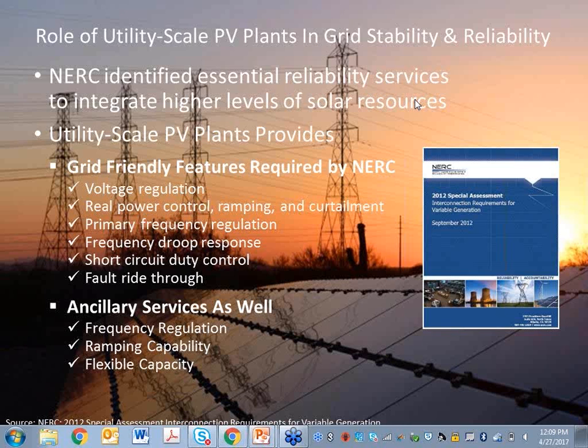What was the maximum power rating for the inverter that has been used? The inverters are 4 MVA. That's why we call it 4 MVA, because essentially if we put 0 reactive power, it would be 4 megawatt in general. If we have some reactive power, we can produce up to theoretically 4 MVARs as well. Perhaps the questioner had some other thoughts.